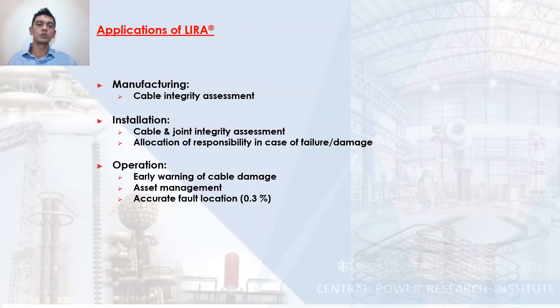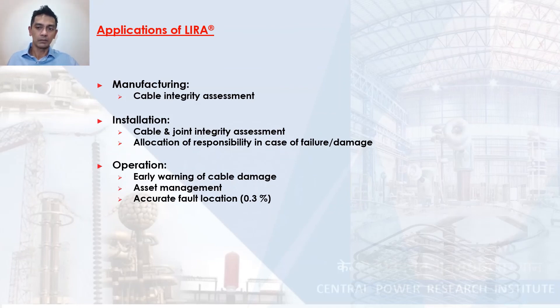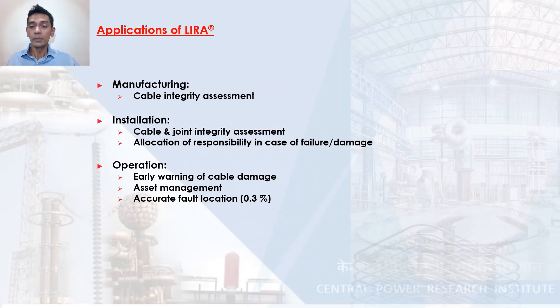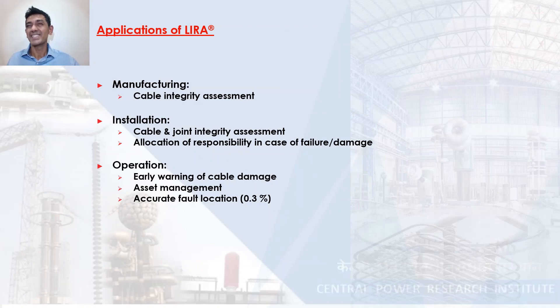Moving on to operations, you can pick up degradation in the cable at a very early stage. This gives you plenty of time to plan the maintenance of your assets and reduce downtime. And in the unfortunate case where there is a cable fault, Lira can pick up the location of the defect with very high accuracy, as much as 0.3%.